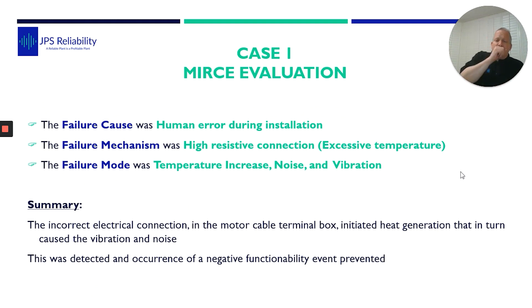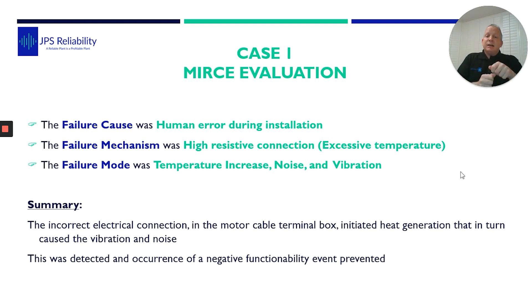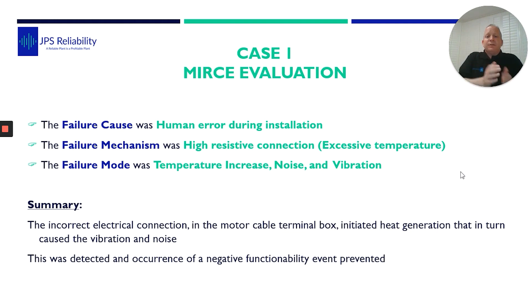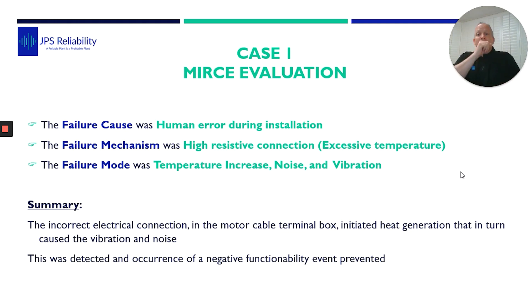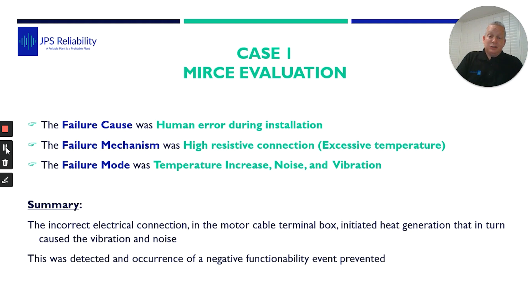So when we stood back and tried to work out what actually happened, we asked: what was the failure cause? Well, three-month-old motor, experienced electrician — unfortunately couldn't have done the connection up to the correct torque. So the failure cause was human error during installation. The failure mechanism was high resistance connection: as those plates were loose and molecules starting to move, generating friction — that's high resistance connection, increasing the temperature. And the mode was temperature increase, noise, and vibration. So the summary is: an incorrect electrical connection — human error — in the motor cable terminal box initiated heat generation, which in turn caused vibration, noise, and the motor to run really badly.